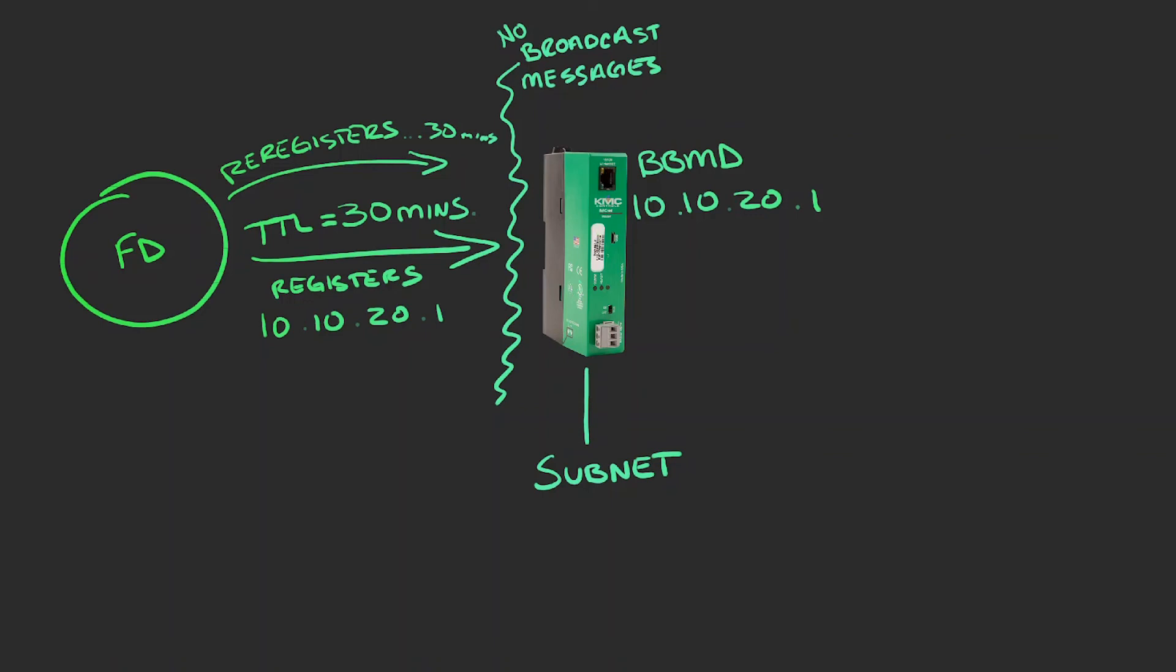Once the BBMD goes live again, it will not recognize the foreign device. Because of this, foreign device configuration is only recommended for short-term or temporary use.